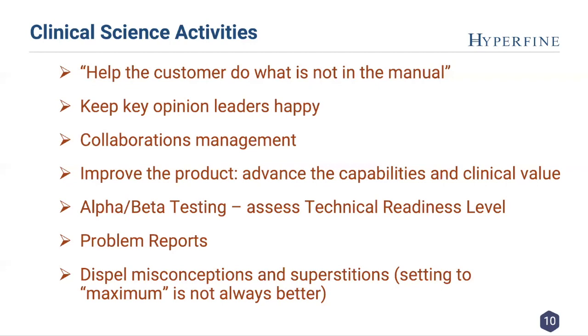A very important lesson I learned many times at Vanderbilt was to dispel misconceptions and superstitions about systems and parameter settings. Setting to maximum is not always better. There's a story where one of the technologists at Vanderbilt, I won't name names, was getting terrible images, and it turned out he had set the water fat shift to maximum. I asked why, and he said he thought maximum automatically meant better. But it created all kinds of artifacts, low bandwidth, and signal drop distortion. So maximum does not always mean better when choosing parameters on an MRI system.